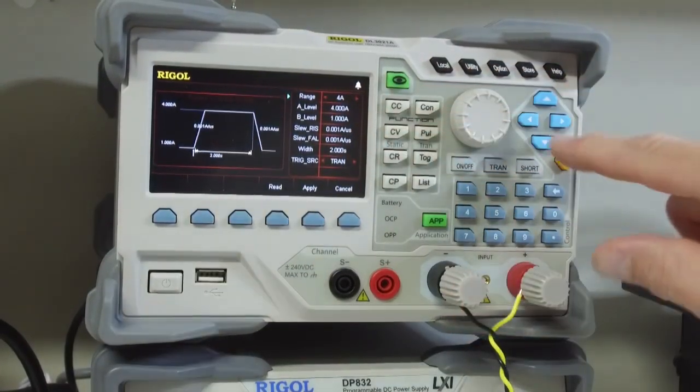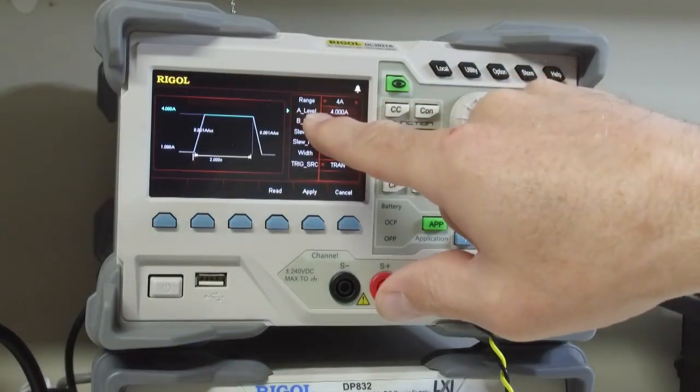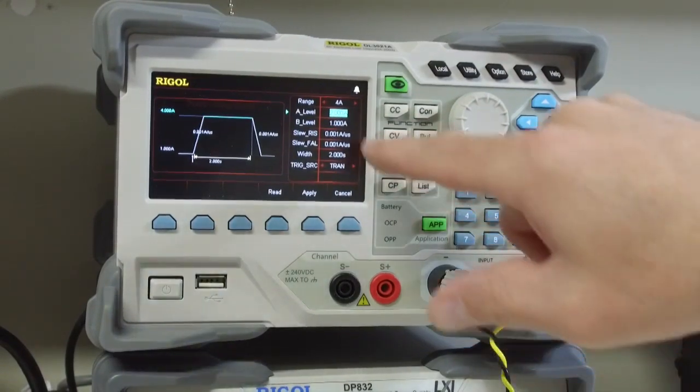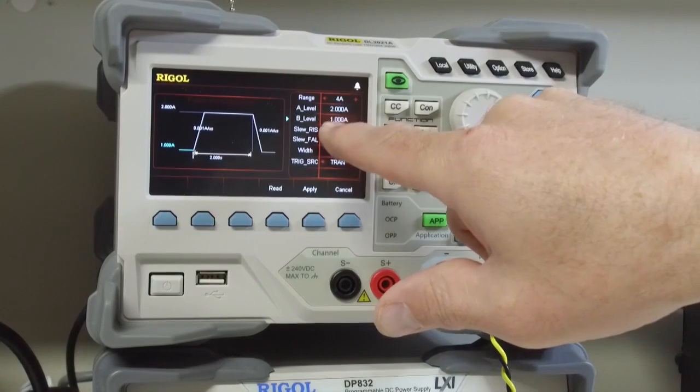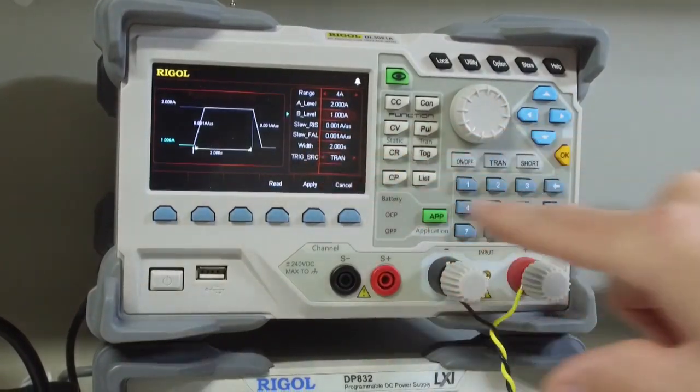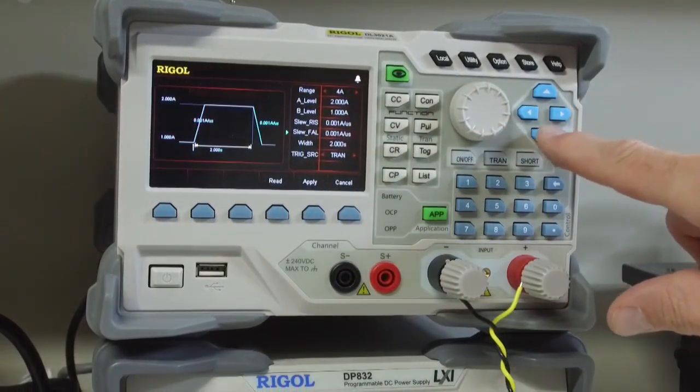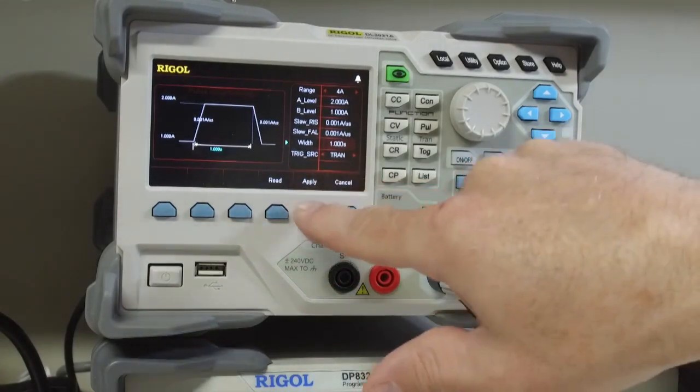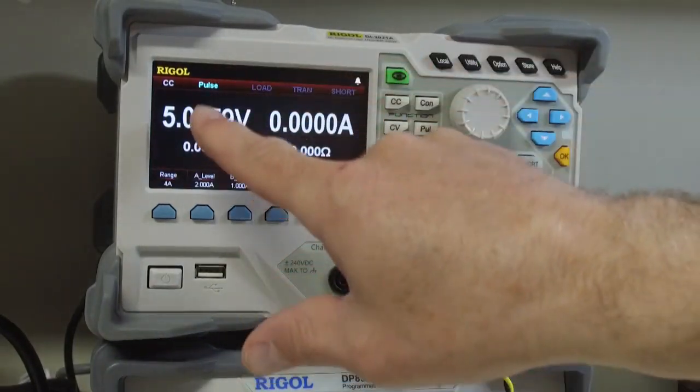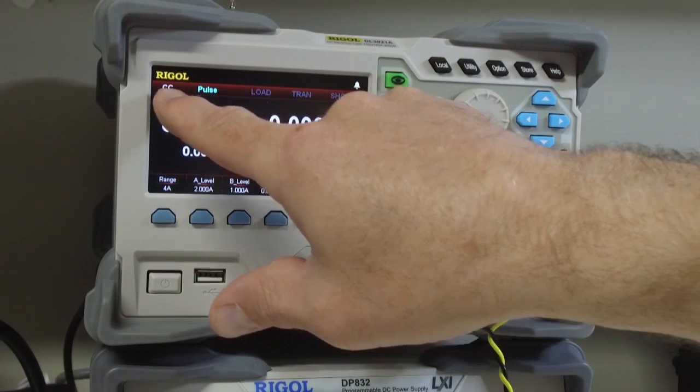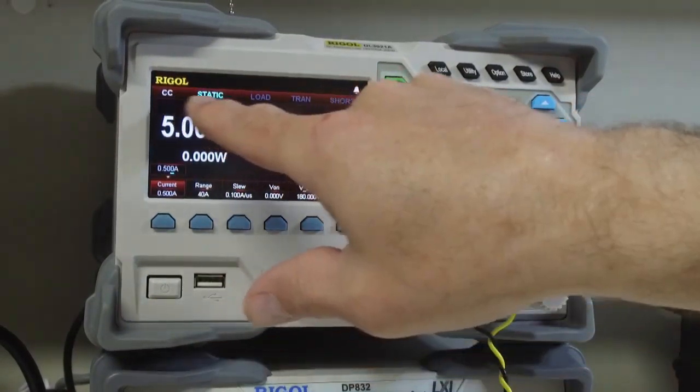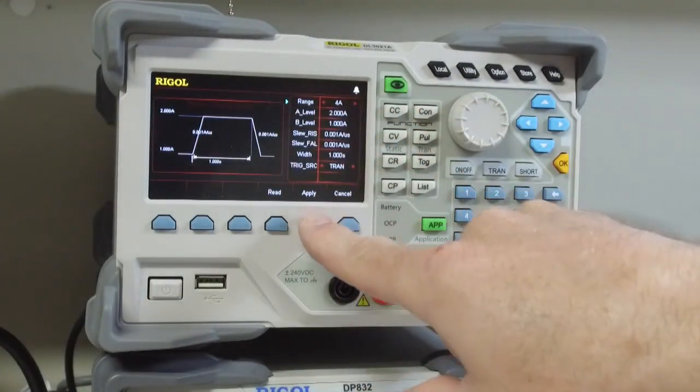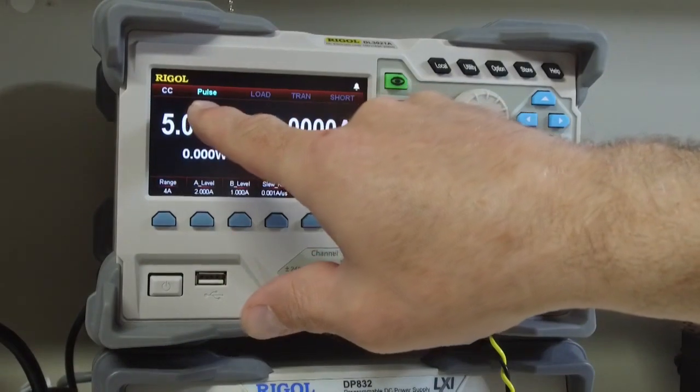So right now, I'm going to set the A level to 2 amps, 2.0. And our B level is set for 1. And I want a width of 1 second. Apply. Now we'll note that the mode I was in constant current, and static. If I want to get back into that pulse mode, I need to hit apply. And so now we're in pulse.